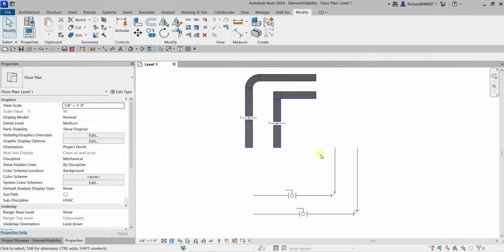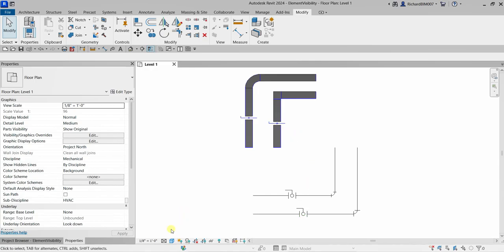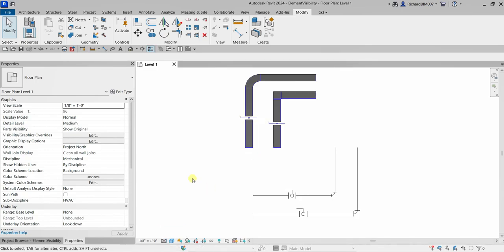If I change this to Consistent Color, this is how it looks. Let me change it to Medium — that's where the changes come in. You'll notice my pipe becomes a single line, and my family as well — my ball valve and also the damper. If I change it to Coarse, all the ducts and pipes will become a single line. So that's why if you ever wonder why your model shows your duct or pipe as a single line, it's because of the detail level setting.